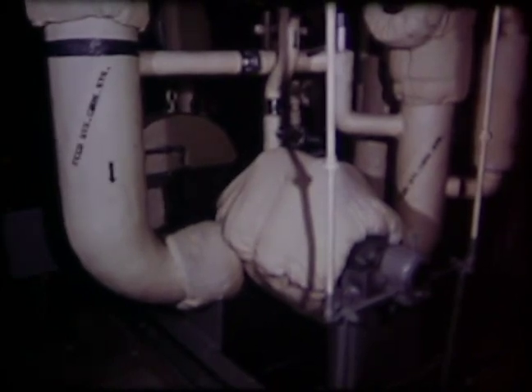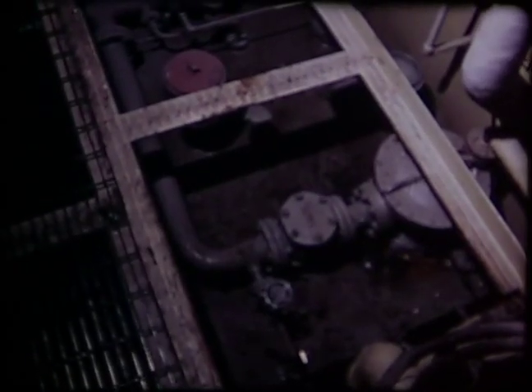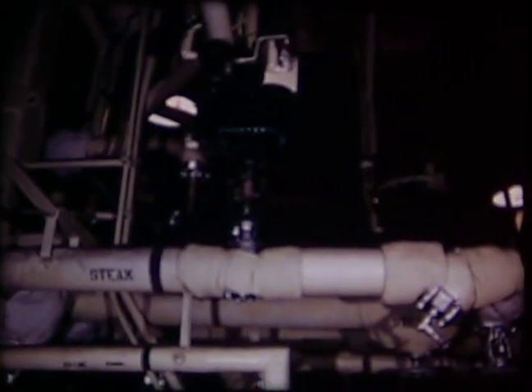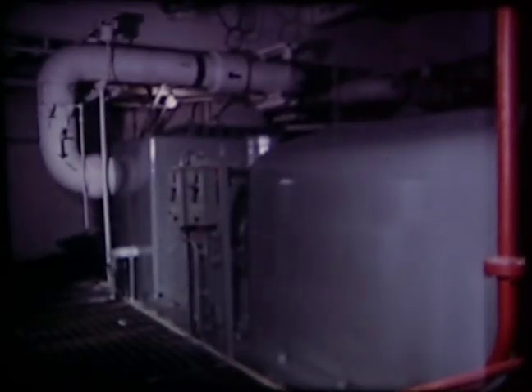A small part of the steam flow, about 6,000 pounds per hour, is used in auxiliary service by units such as the hotel service heat exchanger, the turbine-driven standby feed pump, and the standby lubricating oil pump. For auxiliary services requiring steam at less than main steam pressure, pressure-reducing stations are installed. The main steam flow, approximately 164,000 pounds per hour, drives the turbine generator.